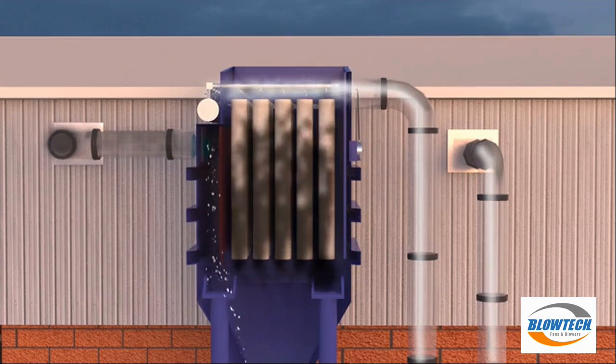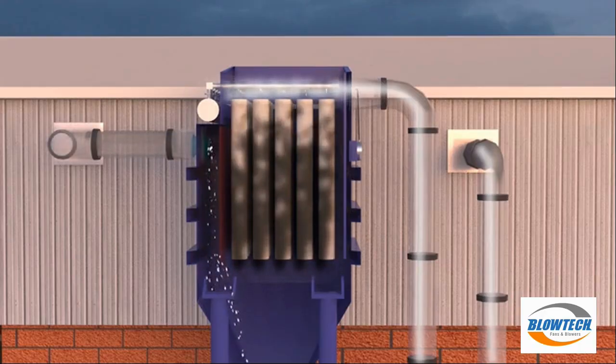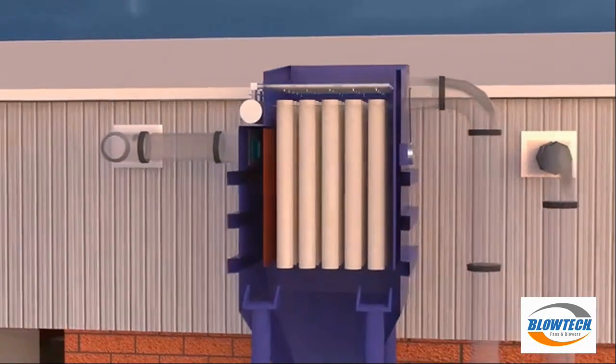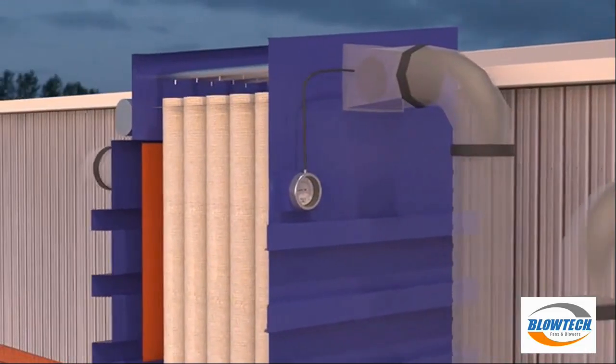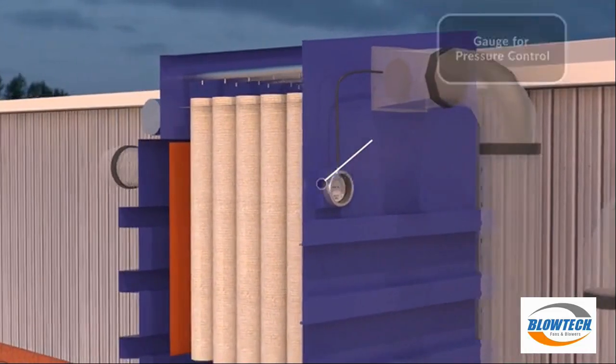This is the general process that takes place in the system. When a certain level of deposit is reached on the filter bags, a pressure is created. This is detected by a gauge fitted on the machine, and this starts the process of cleaning the filter bags.